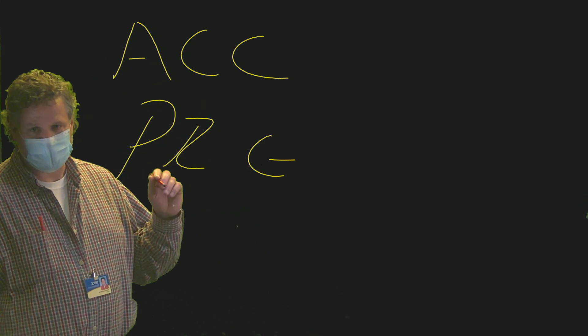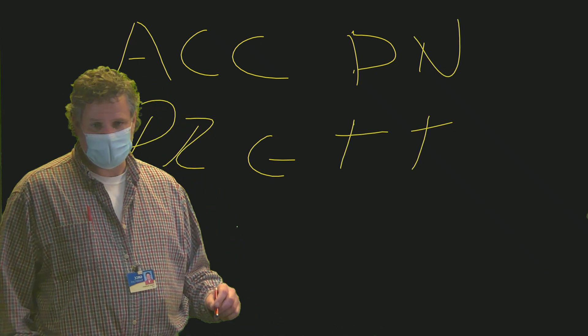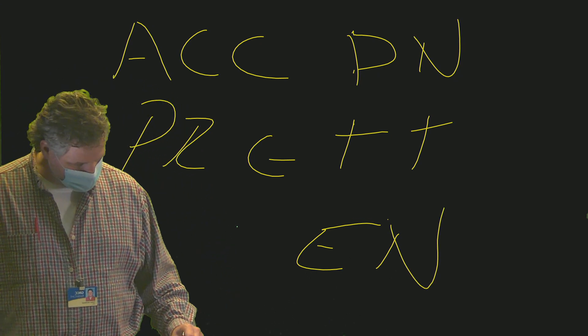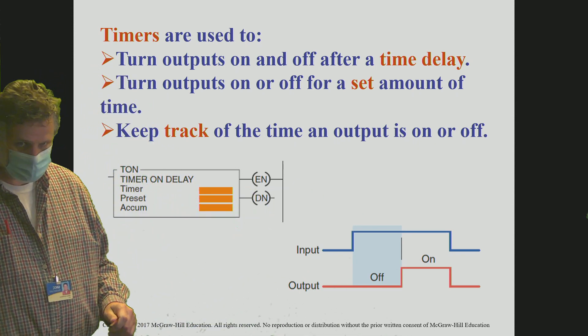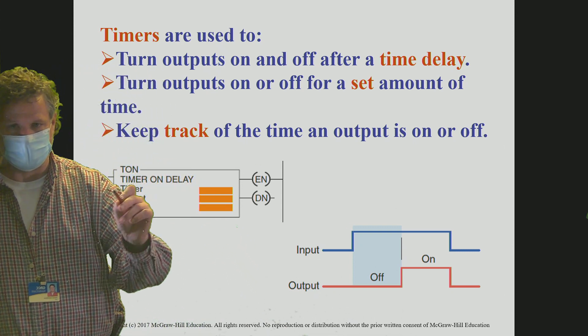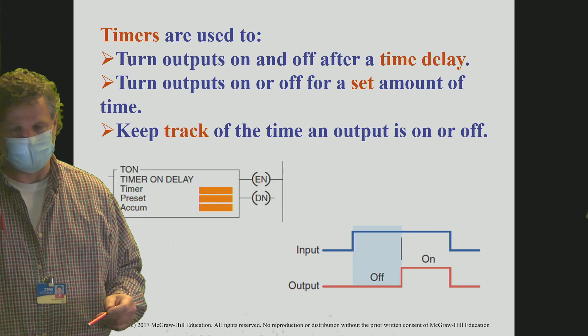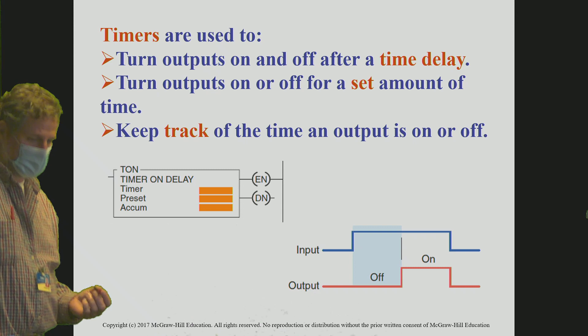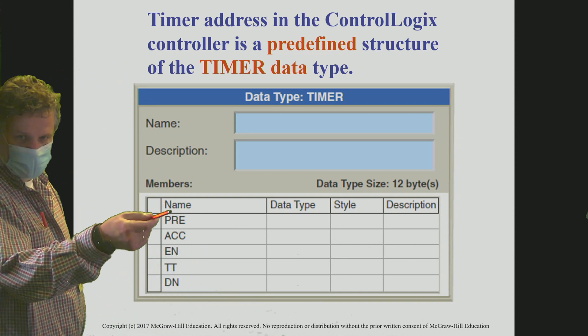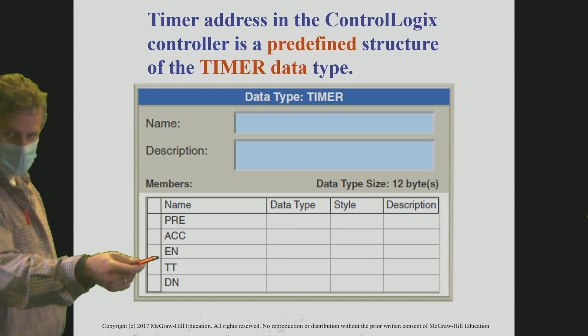We have three bits — one control word — associated with the timer, called the done bit (DN), the timer timing bit (TT), and the enable (EN). When looking at that diagram you can see they illustrate the EN and DN. As soon as the input to this timer comes on, the EN turns on immediately. The done bit turns on once the preset and the accumulated values are equal. Here is the layout of the tags: the preset word, the accumulated word, and then the EN, TT, and done bits.